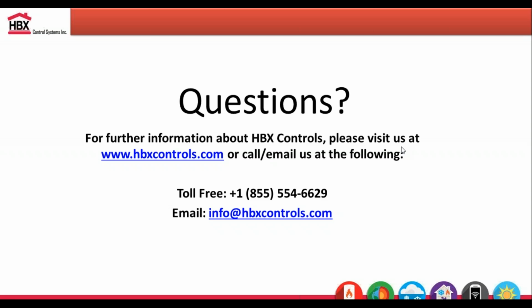Just had a question about the heat pumps. Can you run a hot and chill tank at the same time? You could, but you would need to use two Eco 550s or two Eco 1000s to have that capability. The logic is that if you get a heating and cooling demand at the same time, you can set a priority for that. Whatever you set as priority, or whatever heat demand or cool demand comes first, it'll satisfy that demand first, and then automatically switch over to heating or cooling, if that makes sense.